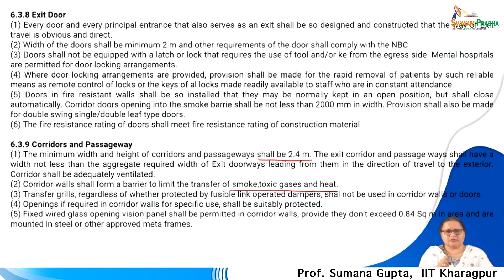So, the mandates for the corridors and passageways are also there, which, as I already mentioned, 2.4 meter is the minimum corridor width for two-way movements, usually for the inpatient side. Corridor walls shall form a barrier to limit the transfer of smoke, toxic gases and heat. Transfer grills, whether protected or not protected by dampers, shall not be used in corridor walls. Openings, if required in corridor walls for specific use, should be protected. Now, these are the major points taken from the National Building Code. So, you can always go through these documents when you are into the actual design, but the key takeaways are underlined or already discussed.